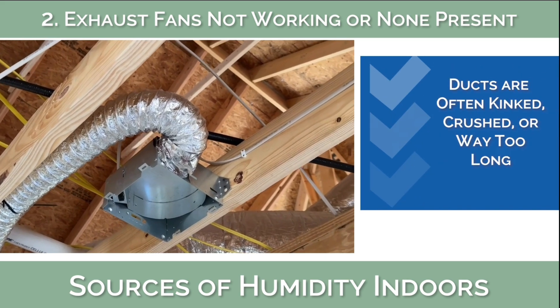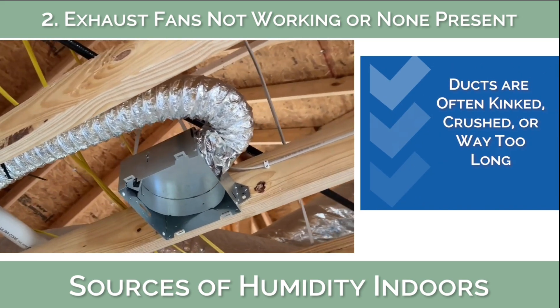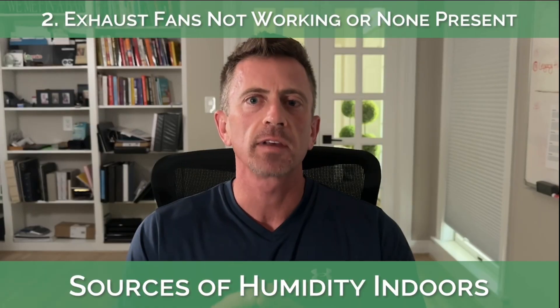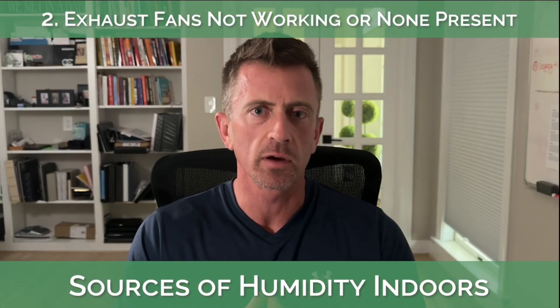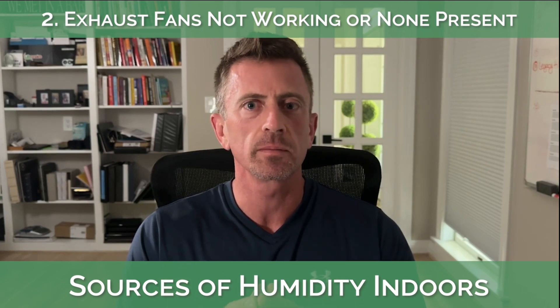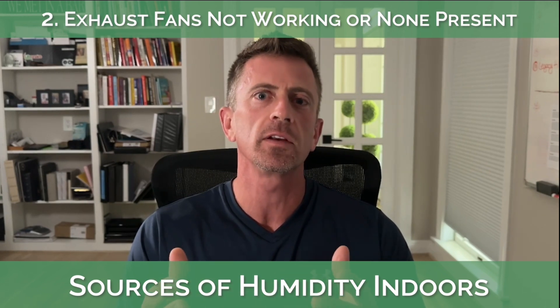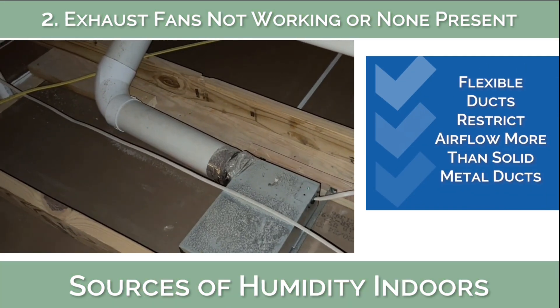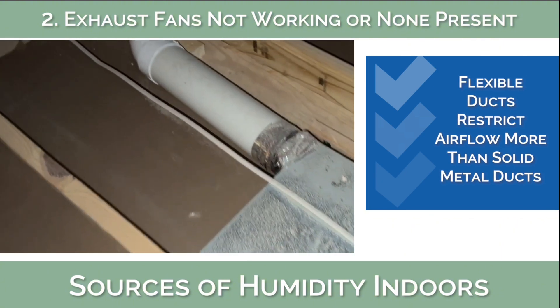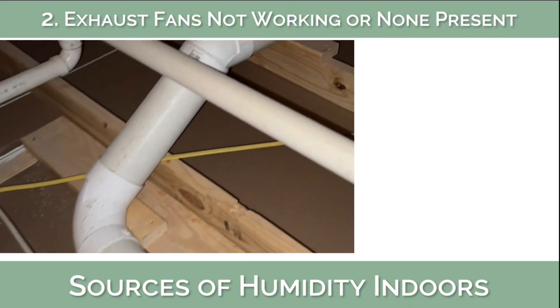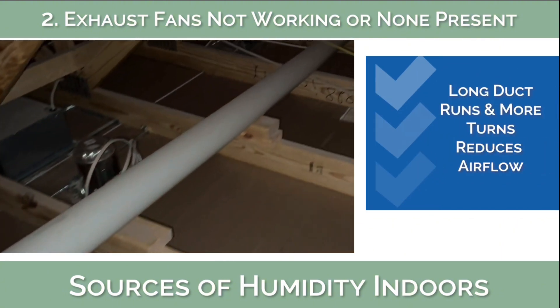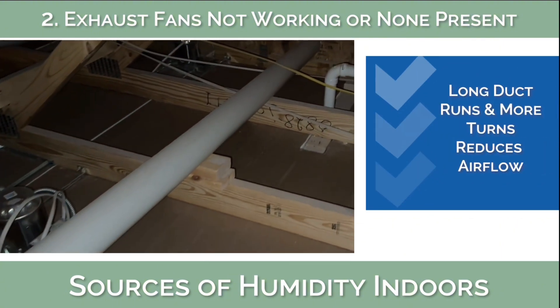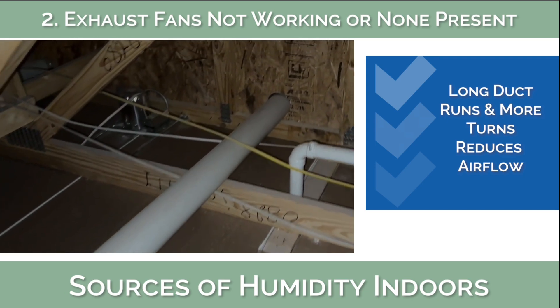In brand new homes, we often find that exhaust ducts are kinked, bent, crushed, or simply way too long to move the amount of air to outdoors that they should. There's a lot of science behind how air flows through ductwork, including exhaust ducts. But the main thing to know here is that flexible ductwork restricts airflow more than solid metal ductwork. And the longer the exhaust duct is, and the more turns and bends are present, the lower the airflow will be through them.